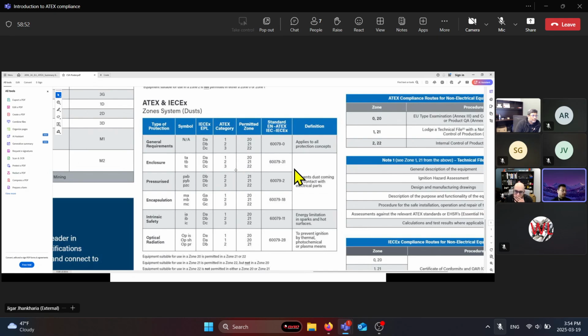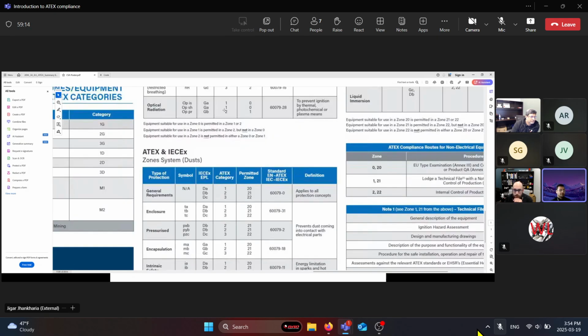Pressurized method of protection is one other one that you can certify. So pretty much anyone using purging or things like that in their product can achieve the zone 20, 21, 22 requirements. Encapsulation as well, intrinsic safety too. And there is another one which is optical radiation, same as gases. So optical radiation in gases is only for zone 0 and zone 1.